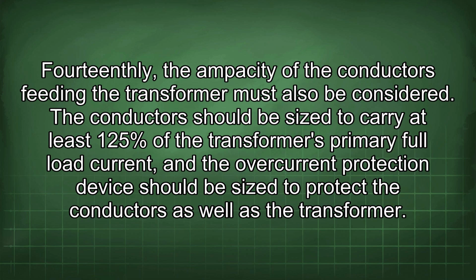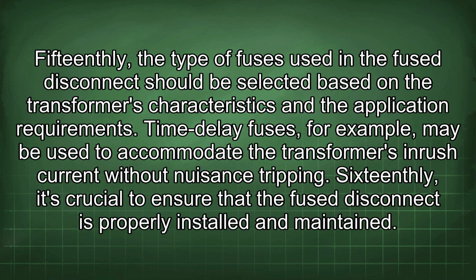The conductors should be sized to carry at least 125% of the transformer's primary full load current, and the overcurrent protection device should be sized to protect the conductors as well as the transformer. 15thly, the type of fuses used in the fuse disconnect should be selected based on the transformer's characteristics and the application requirements. Time delay fuses, for example, may be used to accommodate the transformer's inrush current without nuisance tripping.